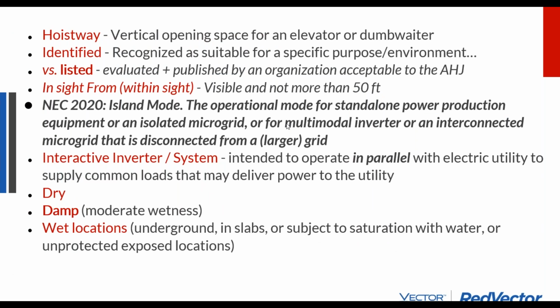Okay, so some other common definitions. Listed means evaluated and published by an organization acceptable to the AHJ. Some local jurisdictions will say only UL listed, and if you want to use another listing agency, you just talk to the inspector ahead of time rather than surprise them at site. But there's no real reason why an inspector wouldn't accept non-UL listings on US sites.